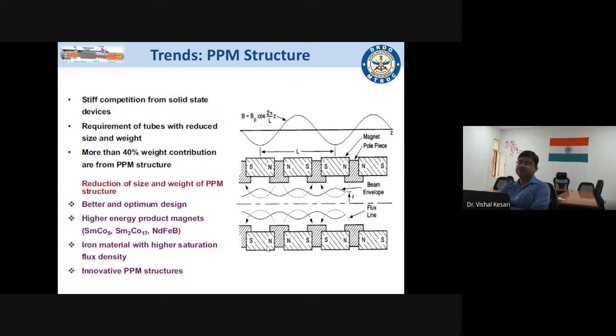The magnetic material which is being used in most of the tubes is samarium cobalt. So actually the two combinations, SmCo5 or Sm2Co17, and then NdFeB. Actually this is the new material. However, things are still going on, because here the magnetic product value is not that high, so for stability and so on, that is not being used. So mostly these two samarium cobalt combinations are being used.